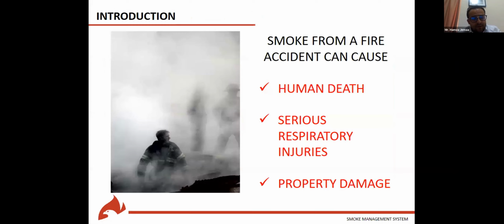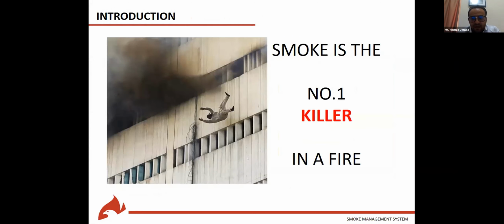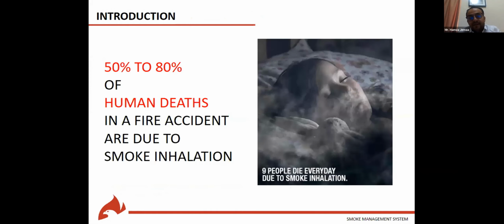It is always important to highlight the consequences of not controlling a smoke inside the building during an accident of fire. Smoke can cause human death, serious respiratory injuries, and damage to the properties. We all know that the smoke is the first killer in case of fire, and 50% to 80% of the human deaths in fire accidents are due to smoke inhalation. Therefore, it is very important to design a smoke control system inside buildings as per the latest international standards like the NFPA, ASHRAE handbook, and to follow the local regulation and guidelines of the Qatar Civil Defense.